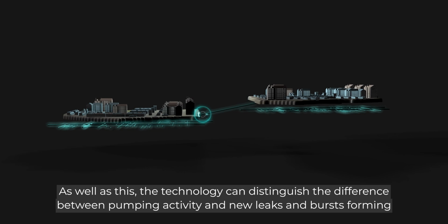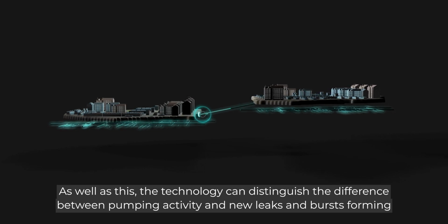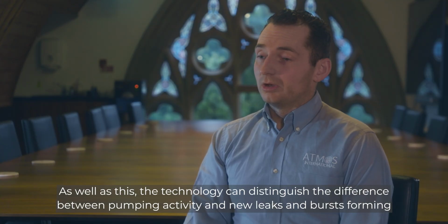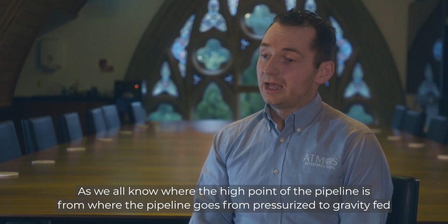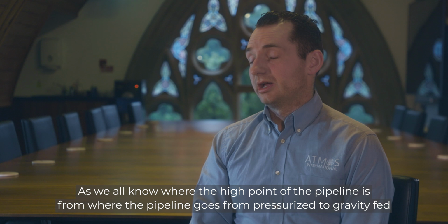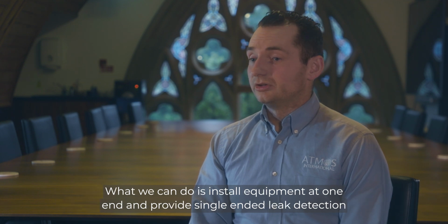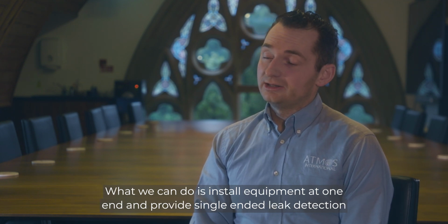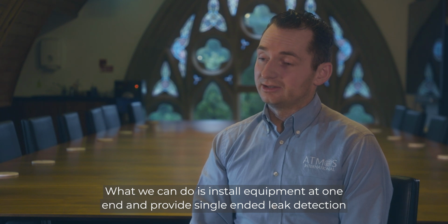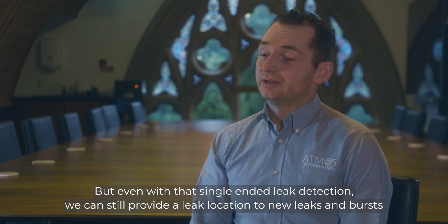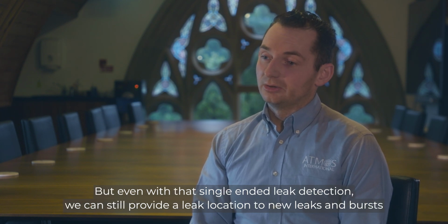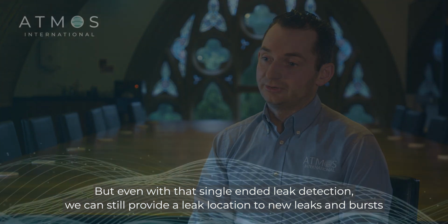As well as this, the technology can distinguish the difference between pumping activity and new leaks and bursts forming. As we all know where the high point of the pipeline is from where the pipeline goes from pressurized to gravity fed, what we can do is install equipment at one end and provide single-ended leak detection. But even with that single-ended leak detection, we can still provide a leak location for new leaks and bursts.